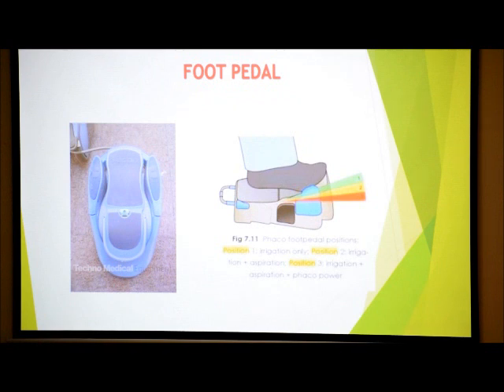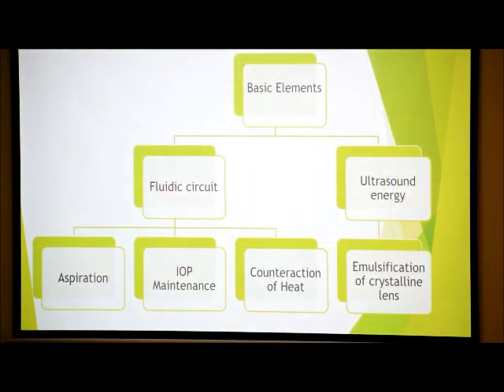Each machine has got a foot pedal, and each foot pedal has got three different steps. The first excursion, there are step 1, step 2, and step 3. First excursion is for irrigation, second one is for aspiration, the third one is for all the three: irrigation, aspiration, and delivering the power. So there are basically two different elements of a phaco system. One is the fluid circuit, and the other one is the ultrasound.